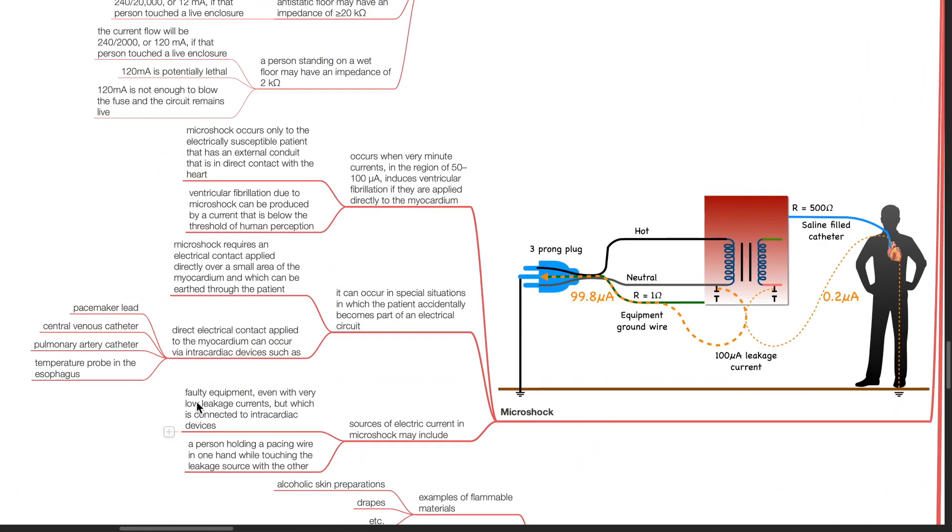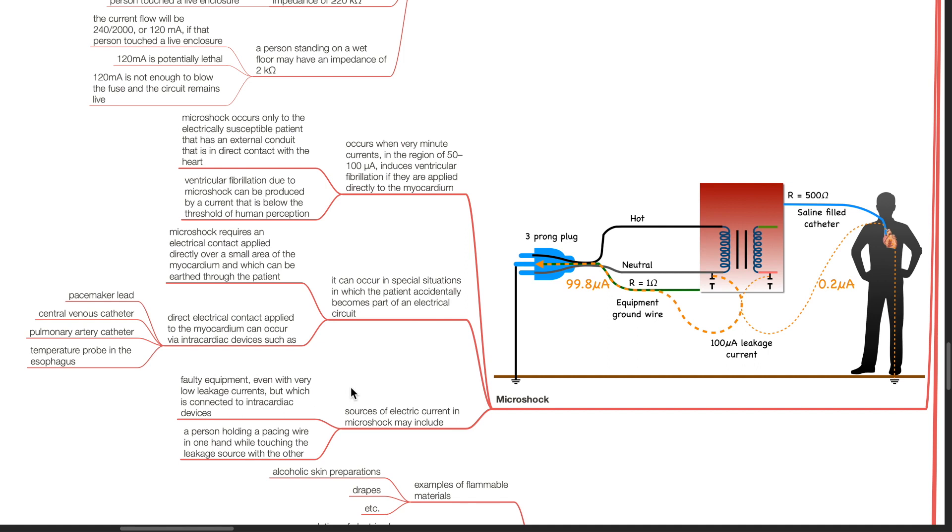Microshock occurs when very minute currents in the region of 50 to 100 microamps induce ventricular fibrillation if they are applied directly to the myocardium. Microshock occurs only to the electrically susceptible patient that has an external conduit that is in direct contact with the heart. VF due to microshock can be produced by a current that is below the threshold of human perception. It can occur in special situations in which the patient accidentally becomes part of an electrical circuit. Microshock requires an electrical contact applied directly over a small area of the myocardium which can be earthed through the patient.